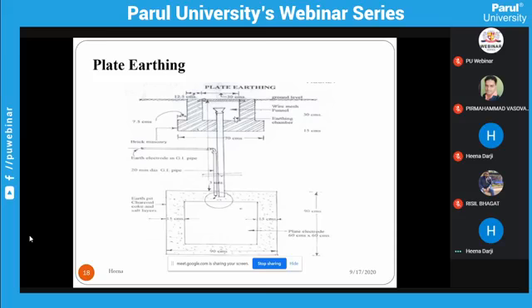This is a diagram of plate earthing. So this is a pit, and you have to put this earthing plate in the ground at a depth of 3 meters, that is, not less than 3 meters. And this is a mesh funnel, so you can put water there for low resistivity. And this is a GI pipe, which connects your equipment and this plate earthing.